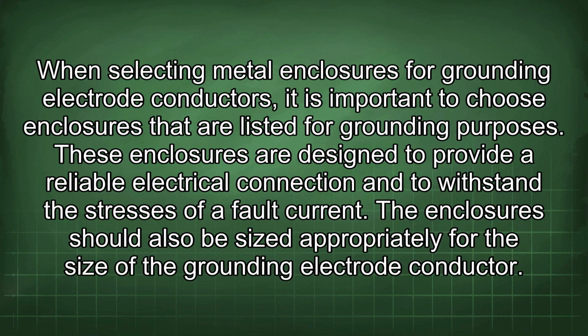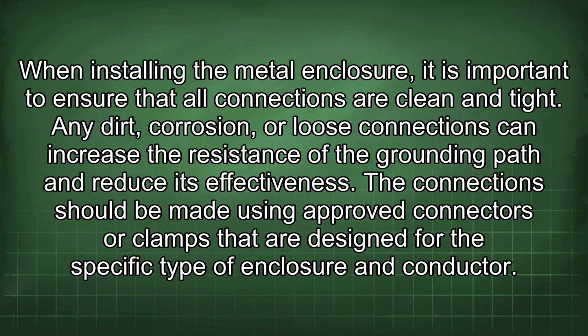When selecting metal enclosures for grounding electrode conductors, it is important to choose enclosures that are listed for grounding purposes. These enclosures are designed to provide a reliable electrical connection and to withstand the stresses of a fault current. The enclosure should also be sized appropriately for the size of the grounding electrode conductor. When installing the metal enclosure, it is important to ensure that all connections are clean and tight. Any dirt, corrosion, or loose connections can increase the resistance of the grounding path and reduce its effectiveness.